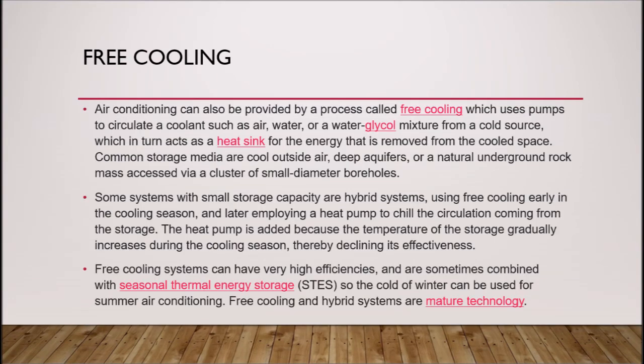Air conditioning can also be provided by a process called free cooling, which uses pumps to circulate a coolant such as air, water, or a water glycol mixture from a cool source, which in turn acts as a heat sink for the energy that is removed from the cool space. Common storage media are cool outside air, deep aquifers, or a natural underground rock mass accessed via a cluster of small diameter boreholes. Some systems with small storage capacity are hybrid systems, using free cooling early in the cooling season, and later employing a heat pump to chill the circulation coming from the storage.